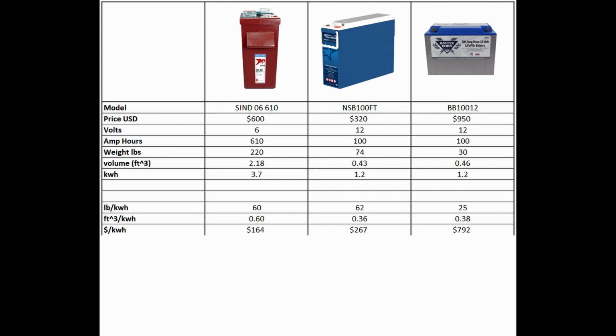Next, let's look at one of the most visible quality factors in a battery decision: cost per kilowatt hour. Here we can see that AGM is about 60% greater cost than flooded, and lithium is 5 times the cost of flooded batteries. So far we're only seeing one benefit from lithium, and that's weight. And unless this is being put in a vehicle or stored in a location where there's a weight restriction, this is a poor reason to choose one battery over another. Even then, at 5 times the cost, it's difficult to justify.